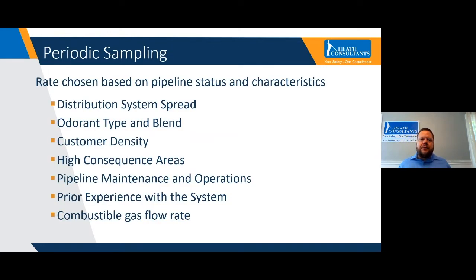So let's talk a little bit about how an operator would determine where and when to take their samples. So periodic sampling is based on many different factors: the pipeline status, characteristics, or excuse me, environmental characteristics as well. So distribution system spread, the type of odorant you're using. Obviously, you're going to want to focus on areas where the customer density is very high, high consequence areas. Also, you're going to want to have a lot of prior experience with your system to know where have we had areas of trouble in the past, where have we had portions of the system that are under-odorized, portions of the system that are over-odorized, and maybe even portions of the system where they have a high leak rate. Another important factor is the gas flow rate, because obviously if you increase the flow rate, you could potentially have an increase in odor detection or odor calls.